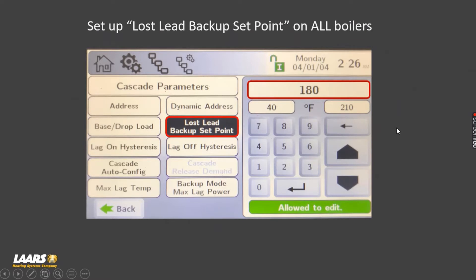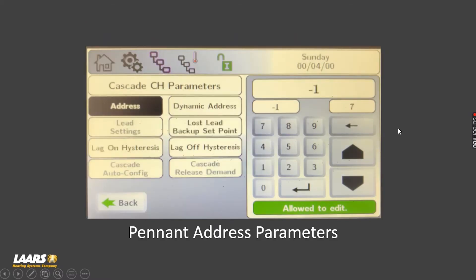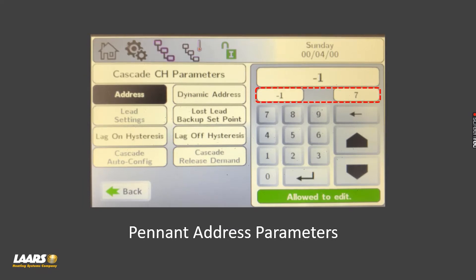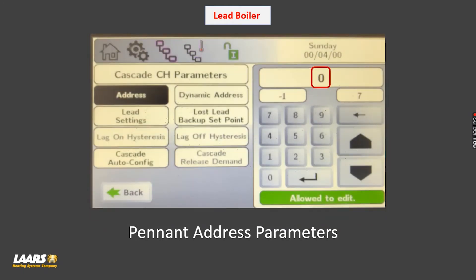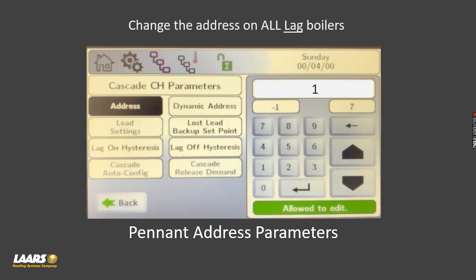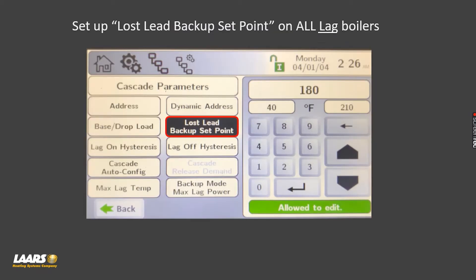Keep in mind the lead boiler will need to be operating and calling for the member boilers in order for them to operate on their own setpoint. Continuing down the line for boiler two, you need to get into the addressing and change that address. The lead boiler is zero, member boilers get one through seven — that is only on the Pennant. The third boiler in line becomes addressed as two. Don't forget you need to go into each member boiler, hit lost lead backup setpoint, and change that value to whatever you need.